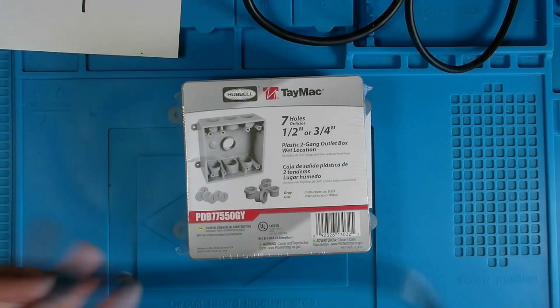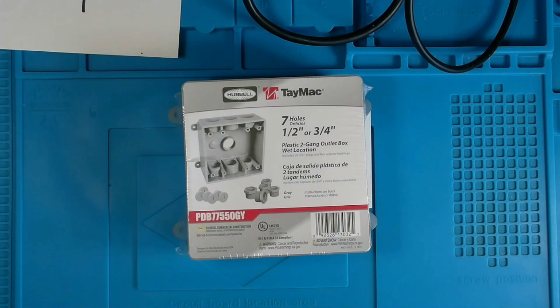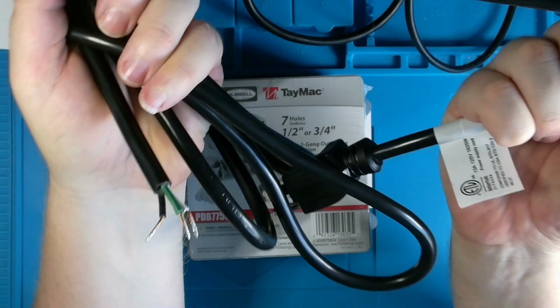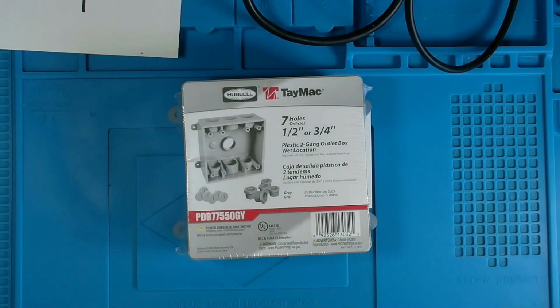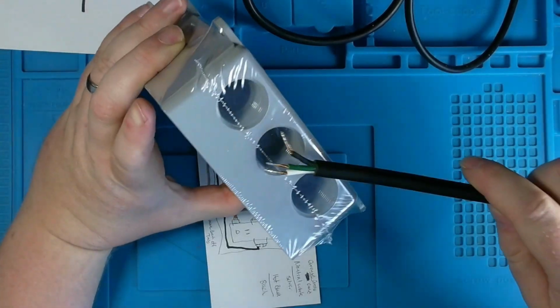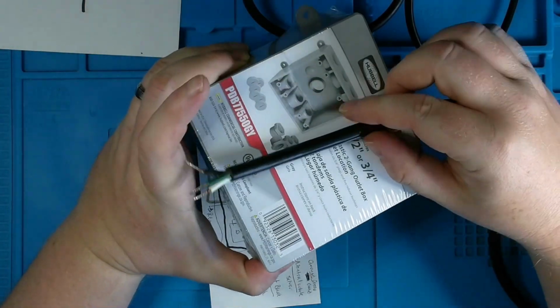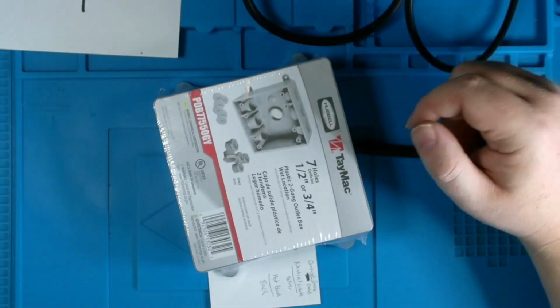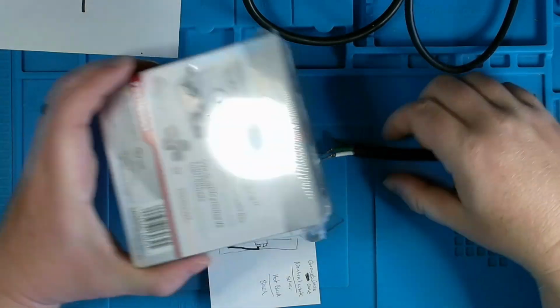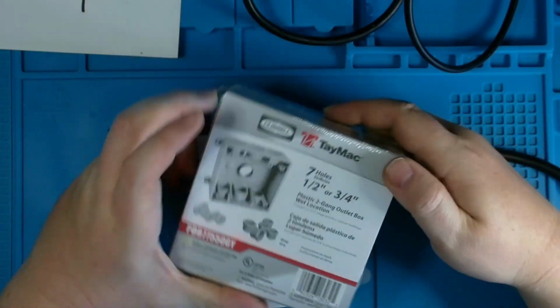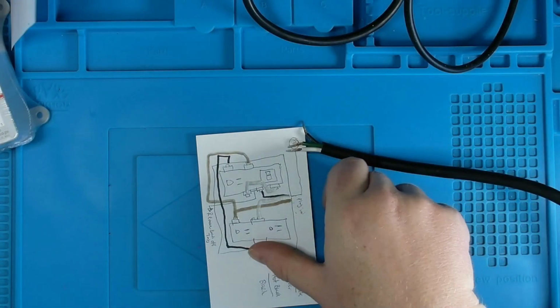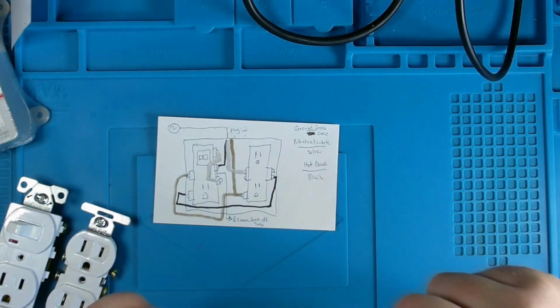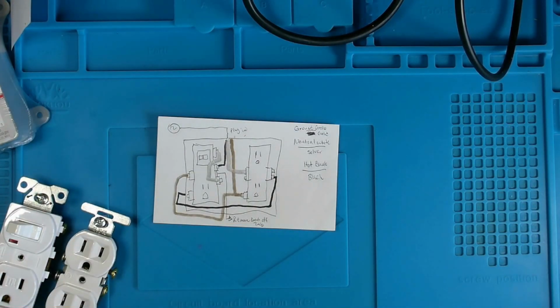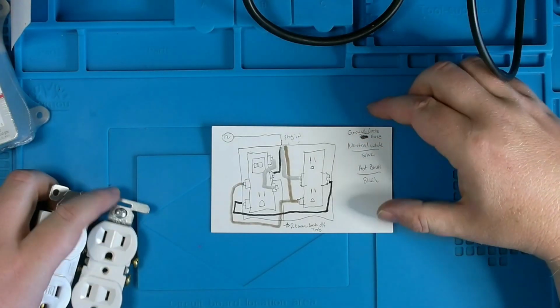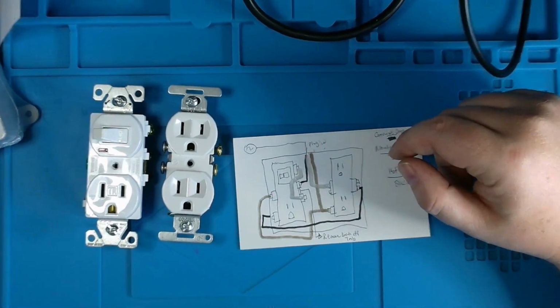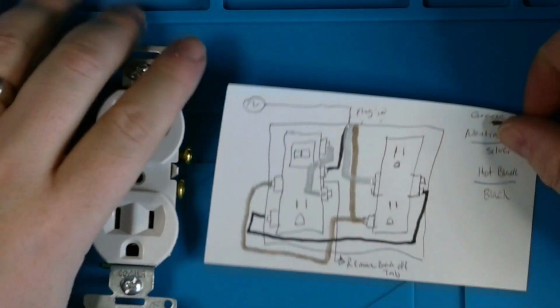To start out with, we're going to take the workshop cord that we bought and feed it through the top part of this 2-gang outlet box. I'm going to put that cable restraint in the top so it can go in and not be pulled back out. Moving on from that, we'll trim this up, cut the leads, and tin some new leads, etc. But here will be the basic setup of how things will be wired inside the box.